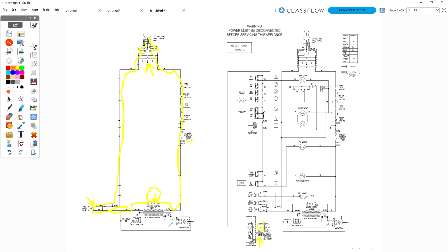That could be if this switch here, the secondary door switch, was failed. Now the primary door switch, when the door is closed, this should be closed as well as the secondary door switch. That just completes a circuit up to the transformer. Now if you look at this, coming from here down to the transformer, if the door's closed, there's 120 here all the time, or at least line 1 coming in. The relay here is on the neutral side of that transformer, and this transformer is waiting for that relay here to close so that the microwaves can happen.